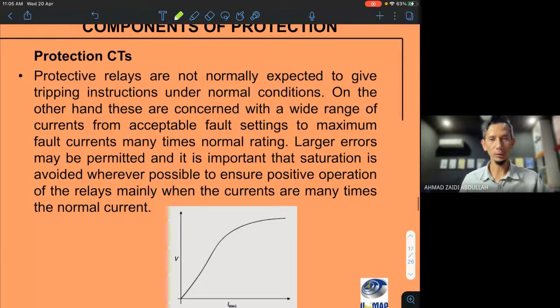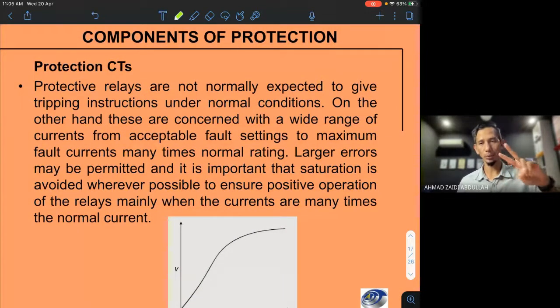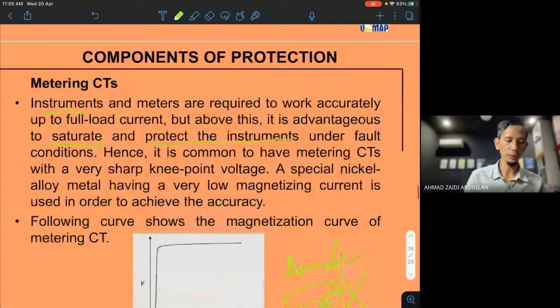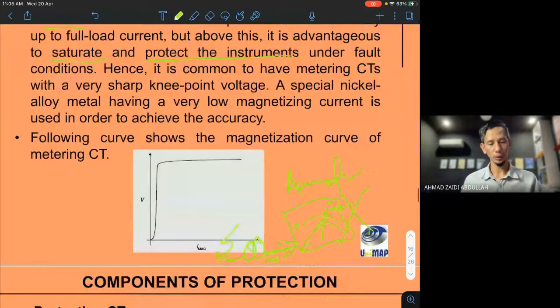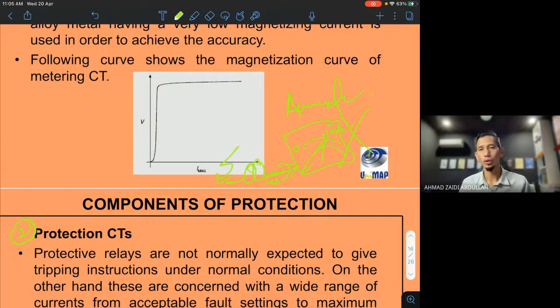And then under relay just now, under CT we have two. Please remember, number one is the metering, number two is protection CT. So normally we use CT for two functions. Either for metering, we use it to save the meter and to make sure the metering functions well. So we need to step down from high current to low current, and from that the metering can function safely, because it is already stepped down to a safe value of current.